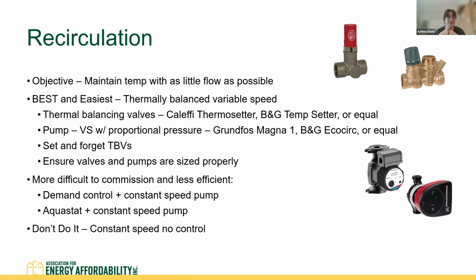The nice thing about this is thermostatic balancing valves are pretty set and forget. You put them to a temperature and that's kind of it. You don't need to go through and balance and calibrate the whole building. Just put them to a temperature and you're done. You just got to make sure your valves and your pumps are sized properly. Options like demand controls and aquastats are much less efficient and much more difficult to commission.